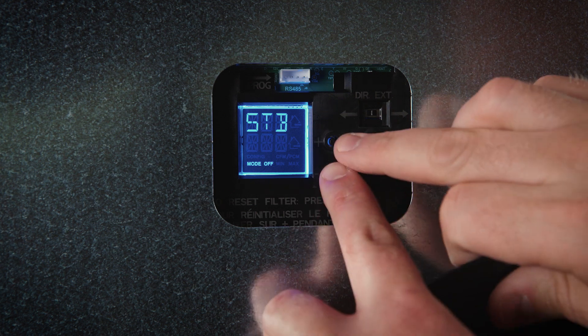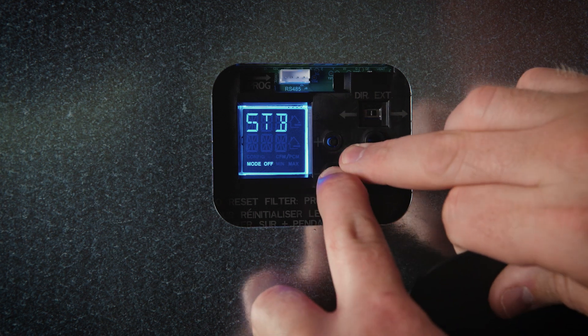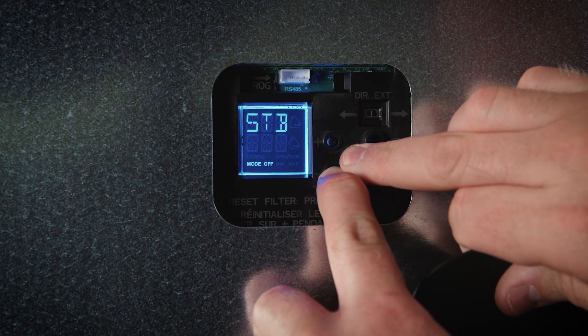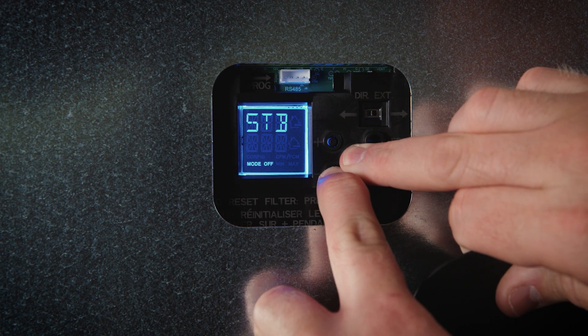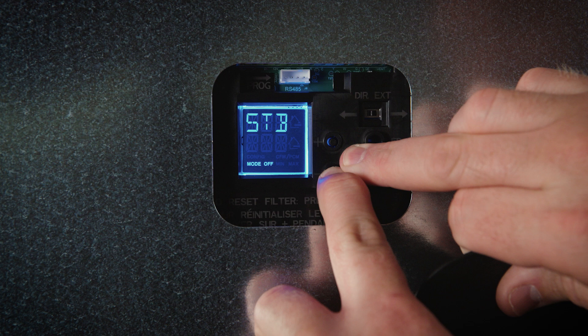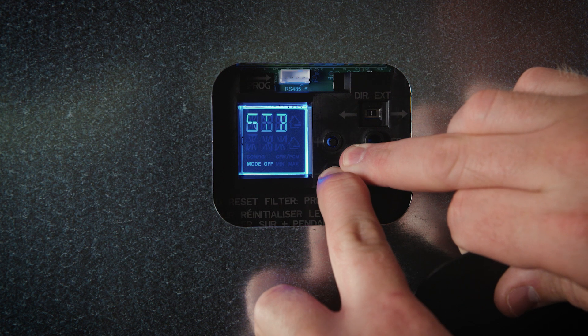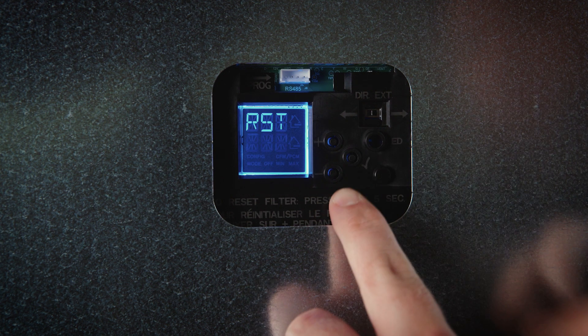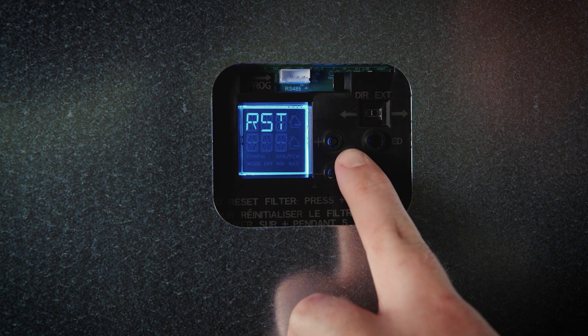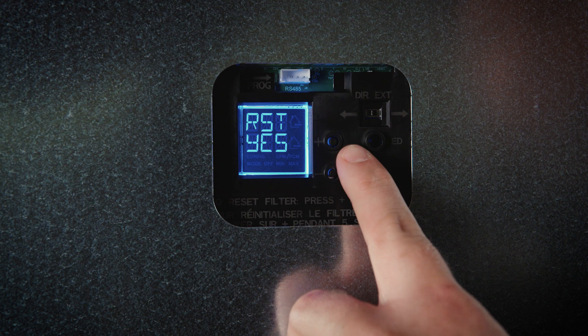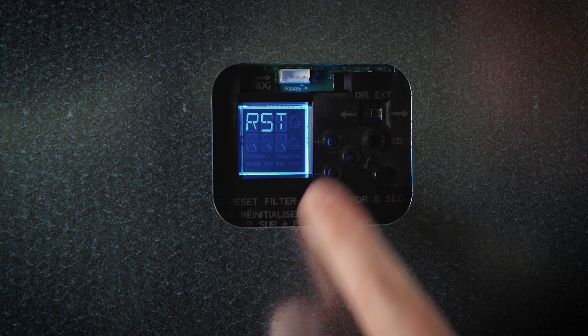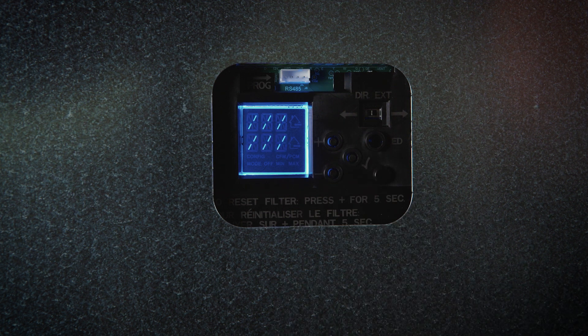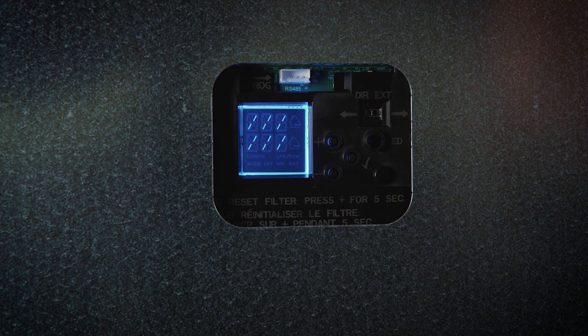If any change is made to the ventilation ducting or to reset settings, press the check mark and minus button simultaneously for 4 seconds. Use the plus or minus buttons to select yes or no and press the check mark button to confirm. Then perform the auto-balancing procedure.